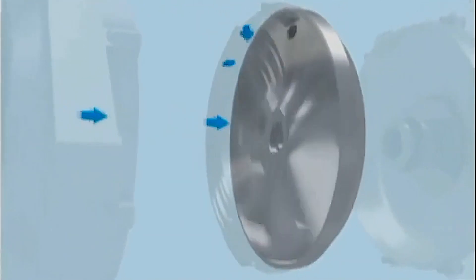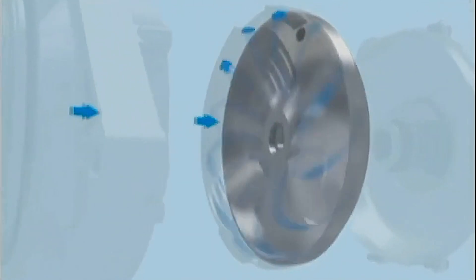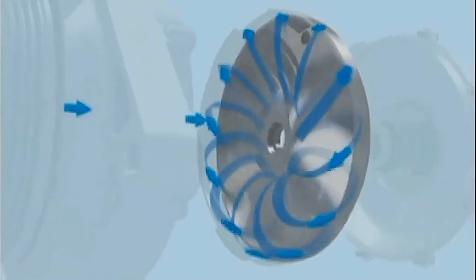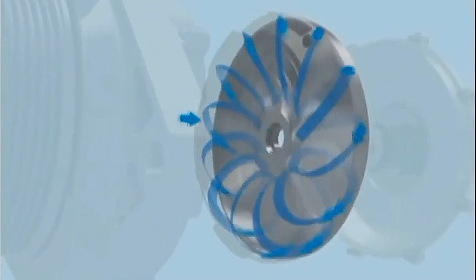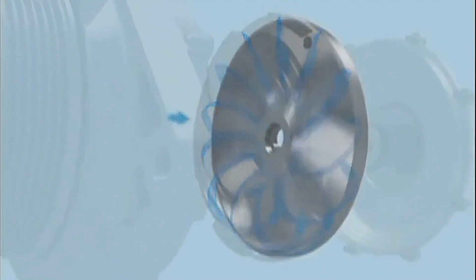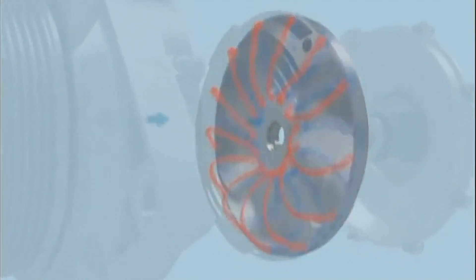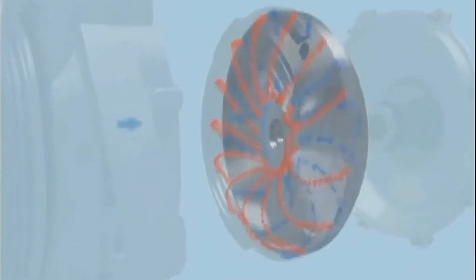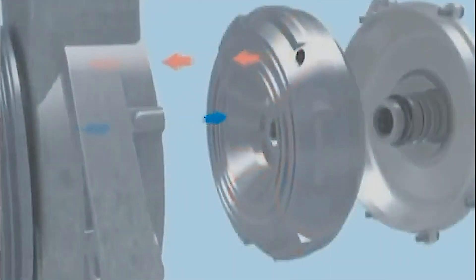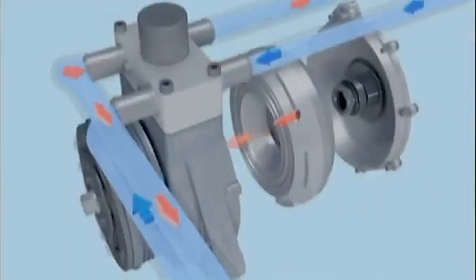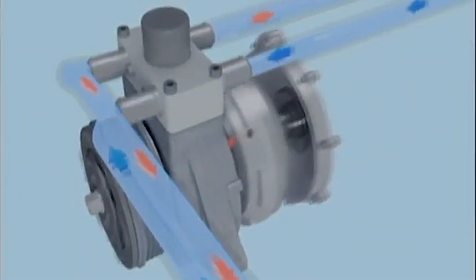The LHG converts the load into coolant heat that is then returned to the engine. The LHG load elevates exhaust gas temperature and ensures that the engine is operating at full engine temperature.